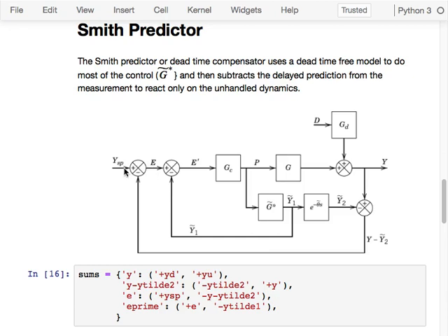So in other words, I've got my normal YSP. Remember, this is 0. I take that, calculate my normal error over here based on my prediction of what's going to happen. I then act only on that prediction, and if everything is perfect, if my model is good, I've now just sidestepped. I've got an early measurement of what the system is going to be doing. So that's obviously if everything is perfect. If I had a perfect model, that's how that would play out.